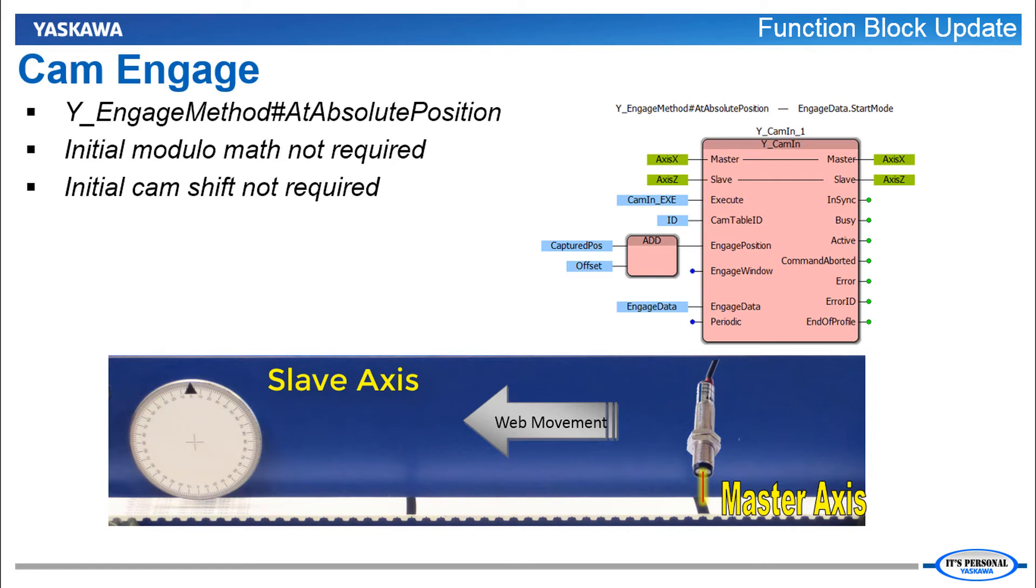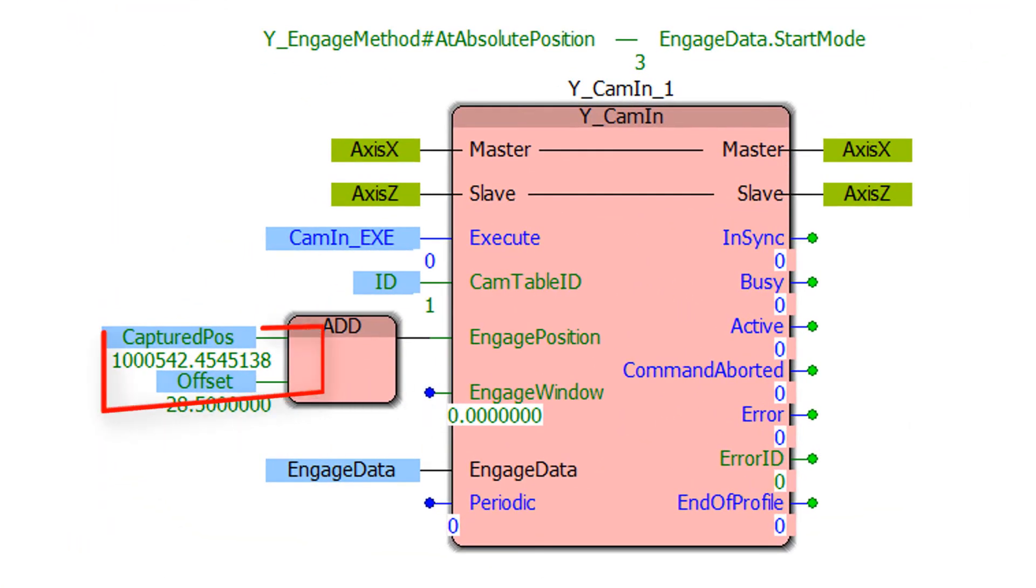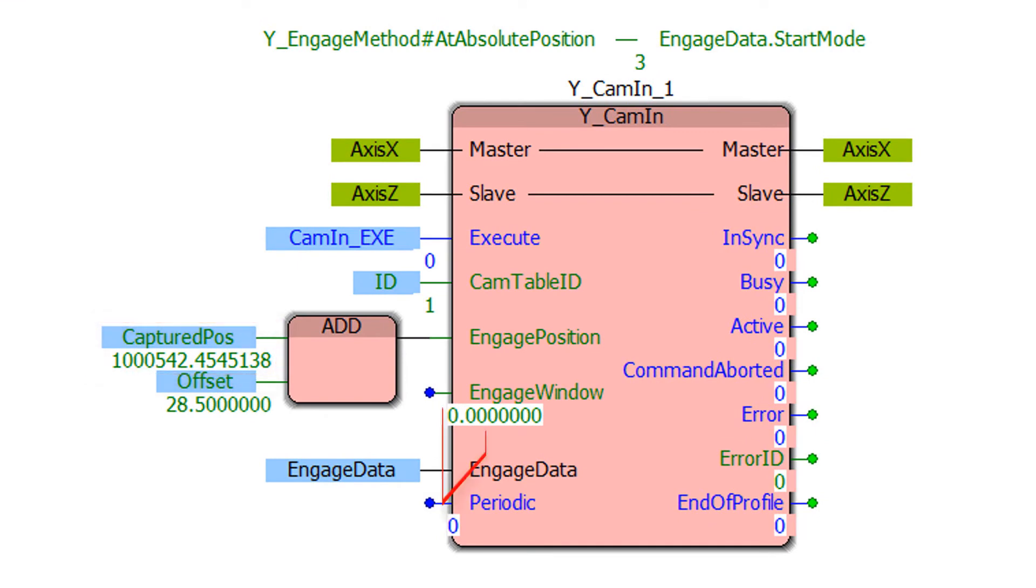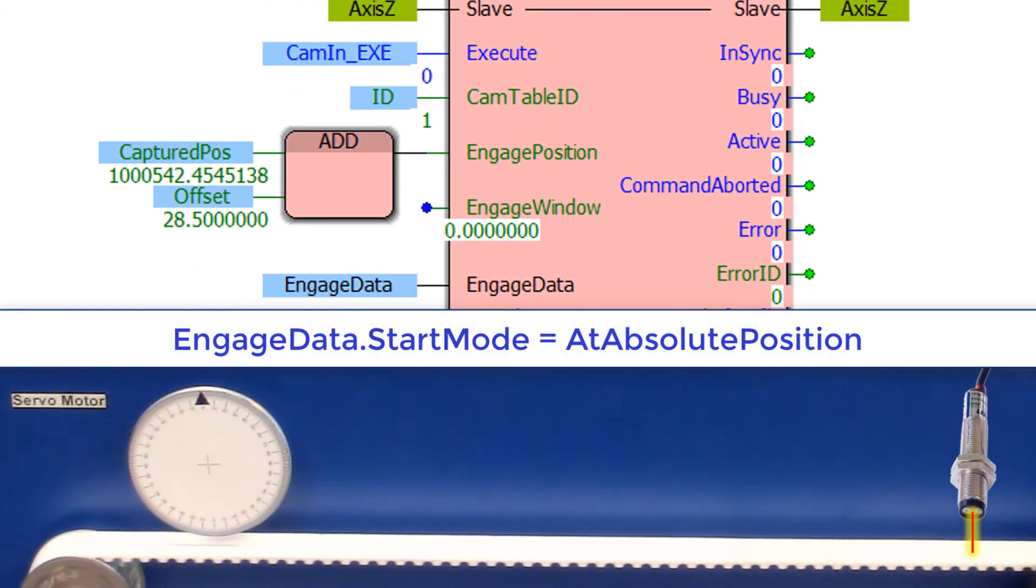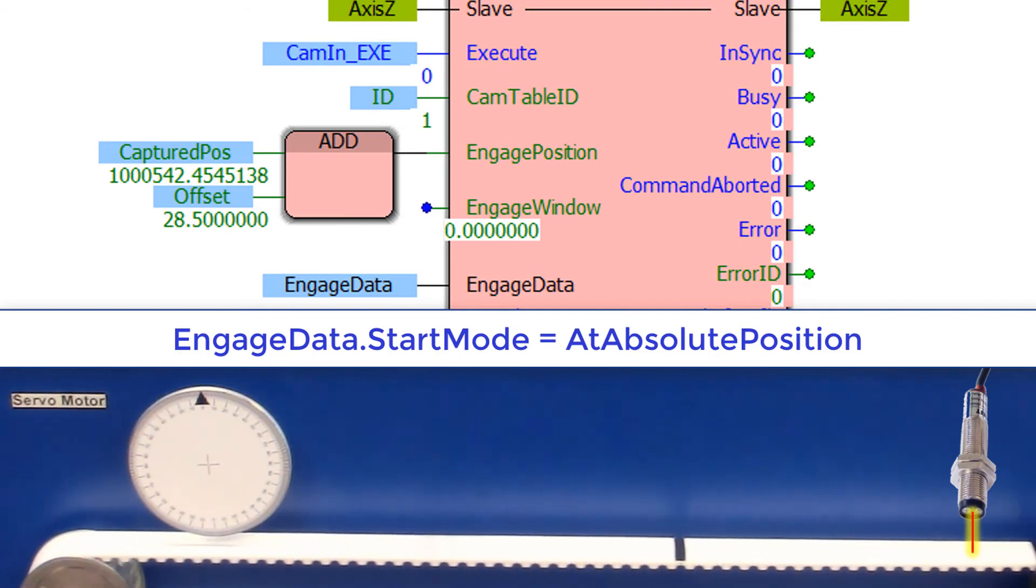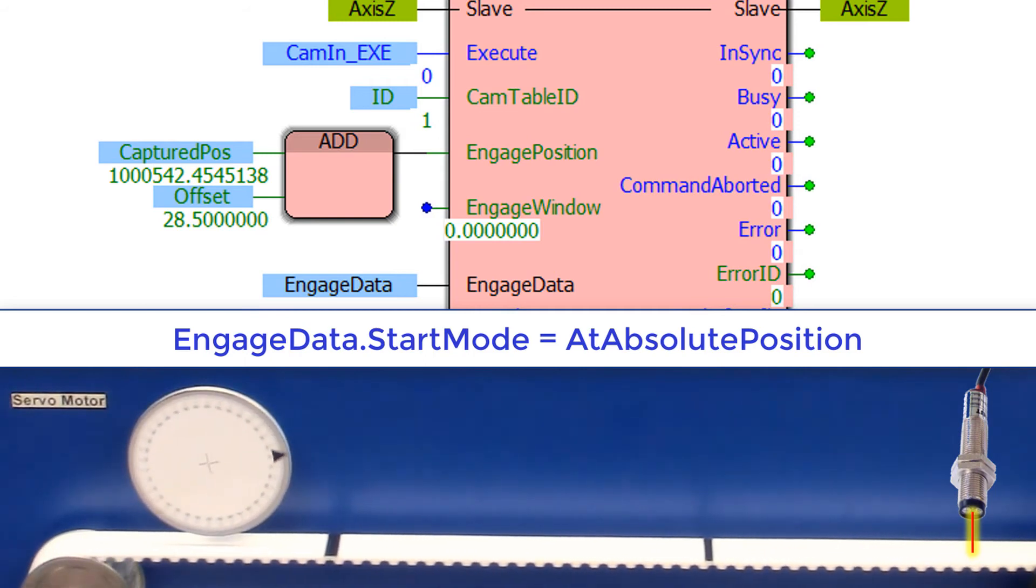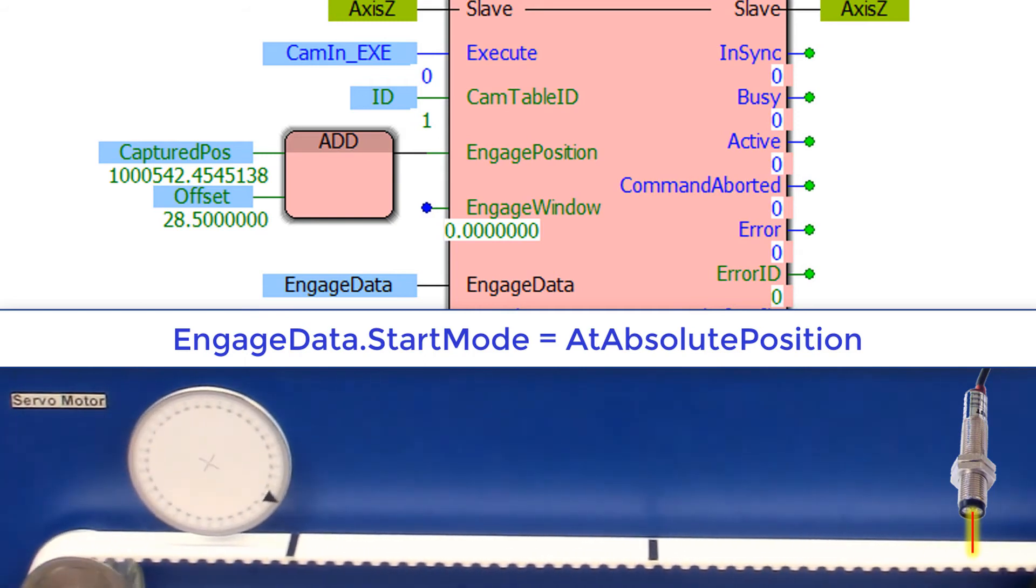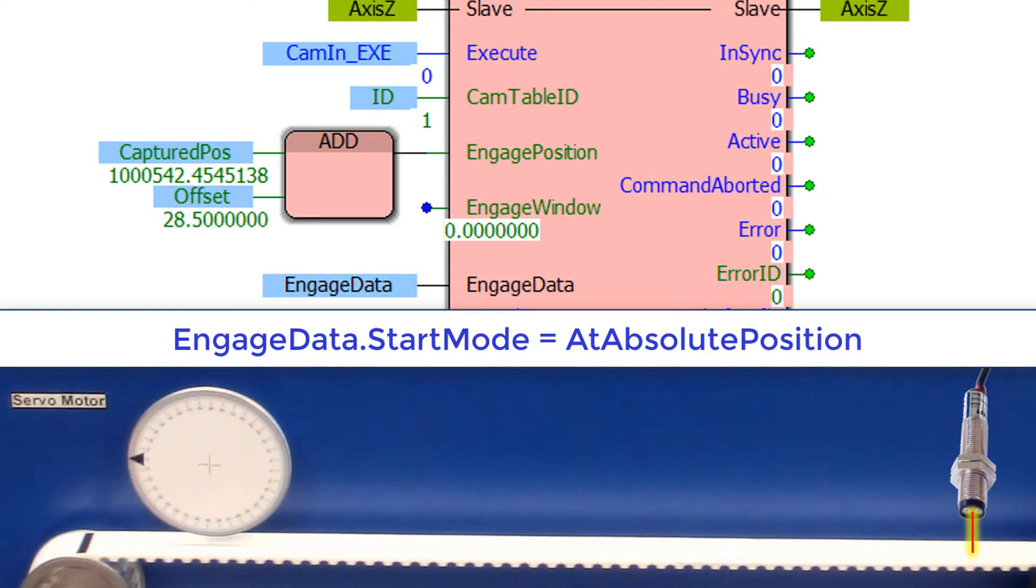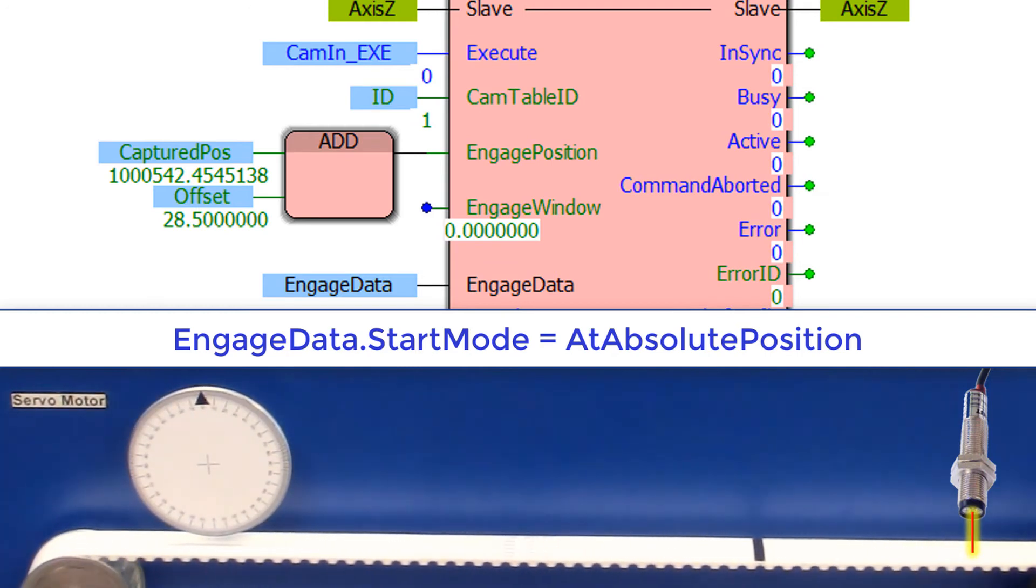For example in a rotary knife application the knife starts disengaged from the master. You write code to capture the master position of the first product. Add an offset. And execute the Y cam in block. The cam automatically engages at the specified absolute position of the master. It is not necessary to write additional code to wait for a number of cam master cycles. Or to calculate an initial shift.